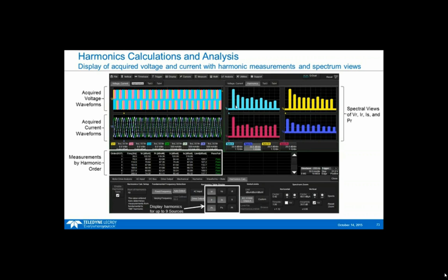And then you can get a spectral display. You can put a cursor on this, look at a value, apply a mask to it if you want, and zoom in on them too. So it gives you a lot of capability to analyze the harmonic root cause of high harmonics.